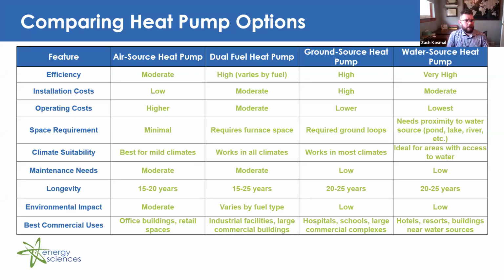So this table provides general trends of various heat pump types. This table should be used for quick comparisons and analysis. But if you are designing a system, you would obviously want to do some more in-depth research. So you can notice some trends here on this table. So starting with efficiency, as we move from left to right, from your air source heat pump, dual fuel heat pump, over to your ground source and water source heat pumps, that efficiency increases. The reason, as I mentioned previously, is that when you're comparing outside air temperature for an air source heat pump as that heat exchange mechanism, when you compare that to ground source or water source, you're likely going to be dealing with much more stable ground temperatures or stable groundwater temperatures. So that will increase your system's efficiency.